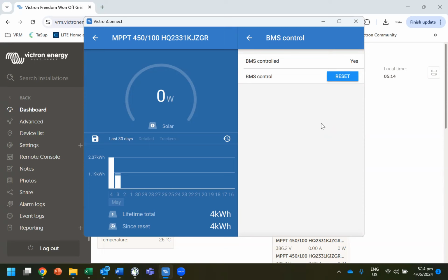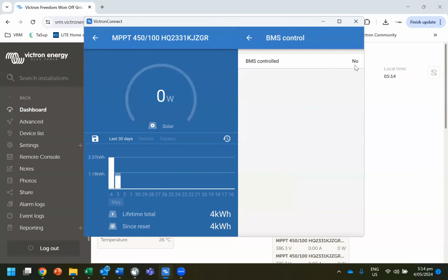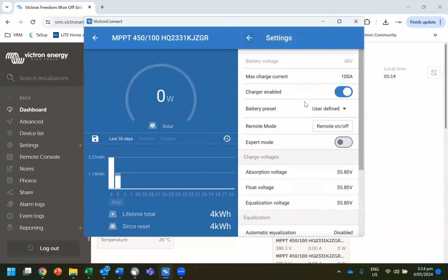However, if there's some kind of problem on the site, then you can unplug the BMS from the battery, or you can go into the remote console and go to services, CAN bus, turn it off. It will then stop communicating with the battery. Then you go into this and you can press reset and it will stay on no. But for now, it's going to go back to yes. Okay, so when it's not on BMS control, see, there we go, it's popped up, it's BMS controlled.